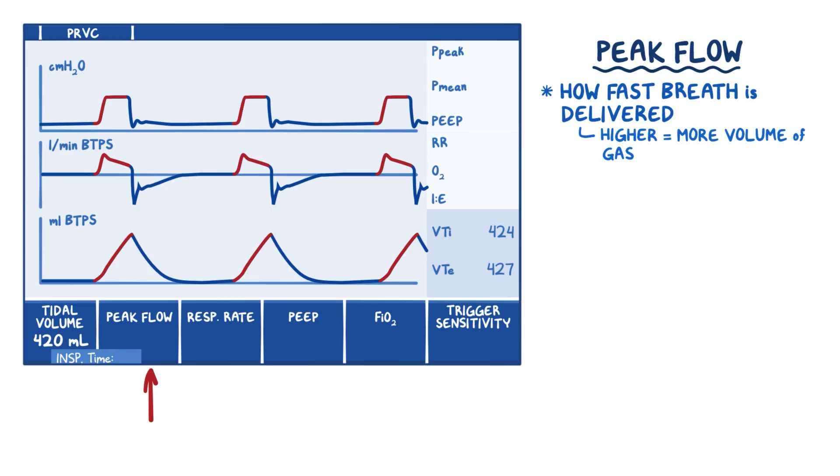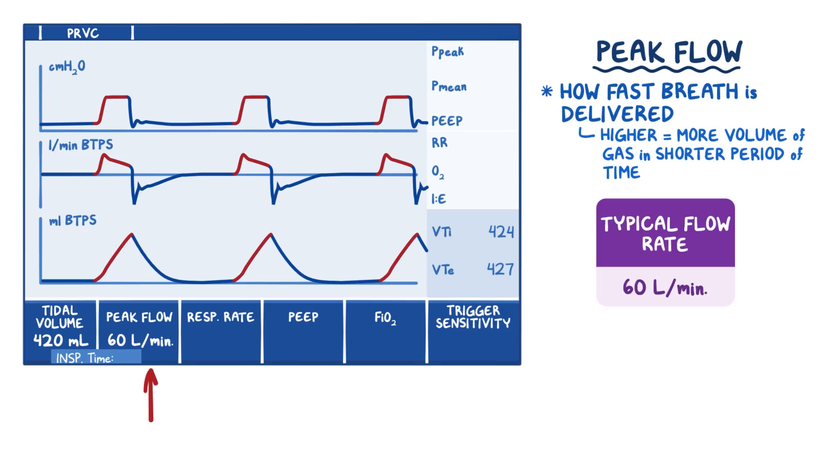Next, we need to set our peak flow, respiratory rate, and inspiration time, which all go hand in hand. The peak flow setting determines how fast we want each breath delivered to our patient. The higher the flow rate, the shorter the length of inspiration. Or in other words, with a higher flow, we have more volume of gas available to deliver a larger amount in a shorter period of time. Typical flow rates are usually set at 60 liters per minute, but can be increased to deliver breaths more quickly if required.